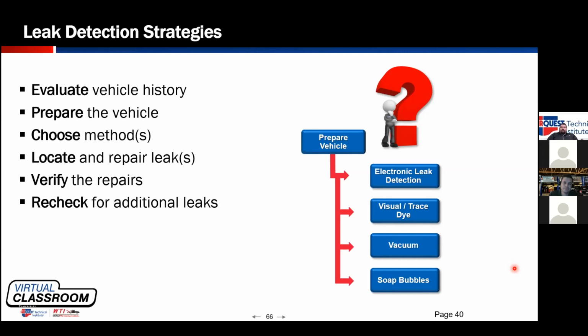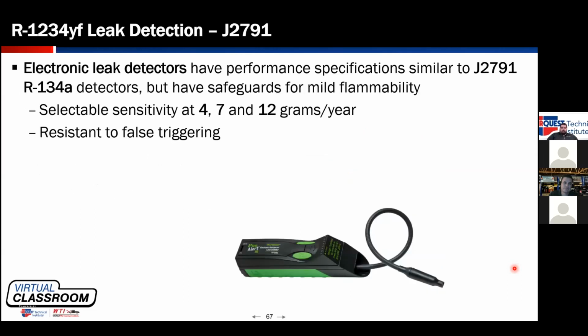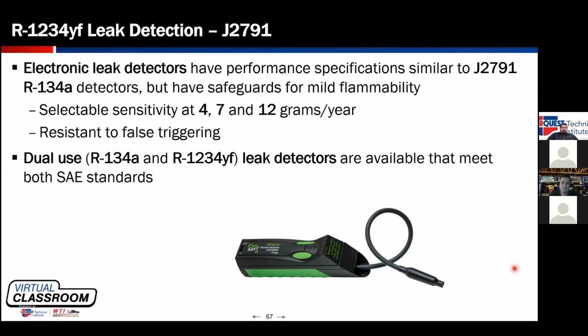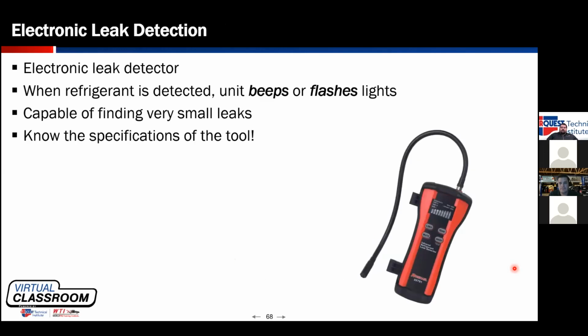One big mistake a lot of guys make is you find one leak and stop looking. Make sure that even if you find a leak the first place you look, that you still go back and check the rest of the system. Part of the standard for leak detection is the detectors have multiple settings. The sensitivity settings built into the tools are 4, 7, and 12 grams per year. Generally, what I like to do is start with the lowest sensitivity setting, so 12 grams per year, and work my way down. The lower sensitivity I'm on, generally the less likely I am to false trigger. As you said, most of the detectors that are 2913 do meet 2791.